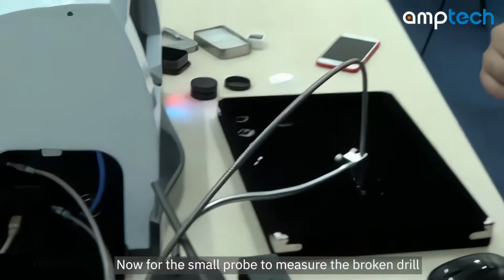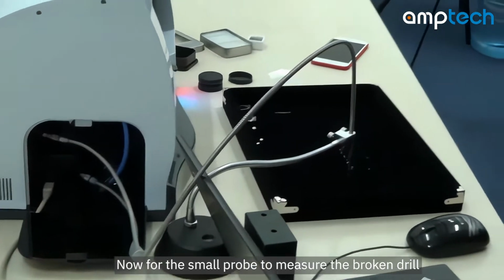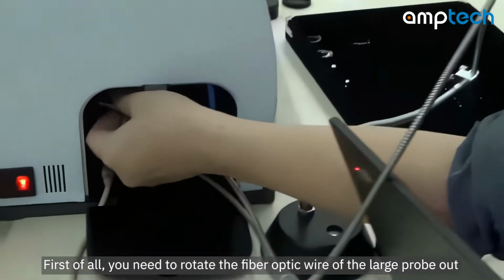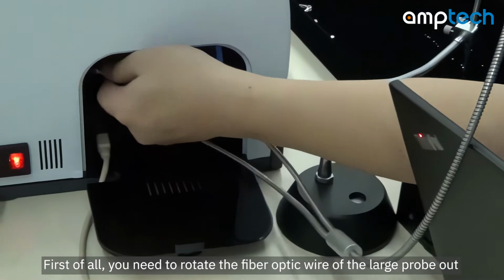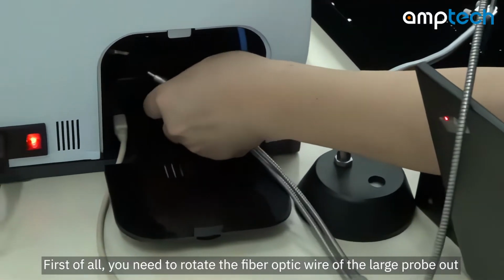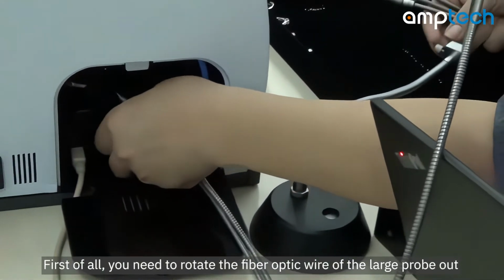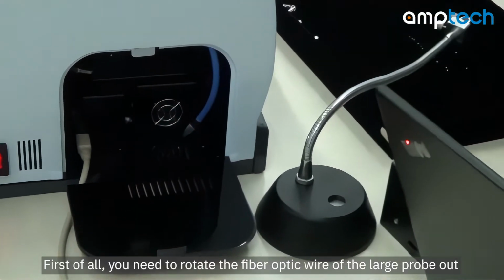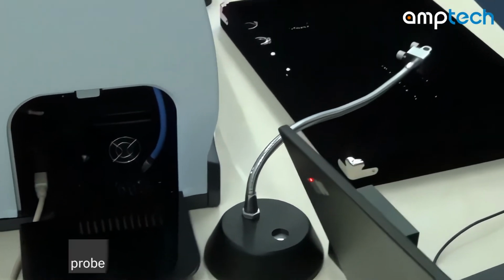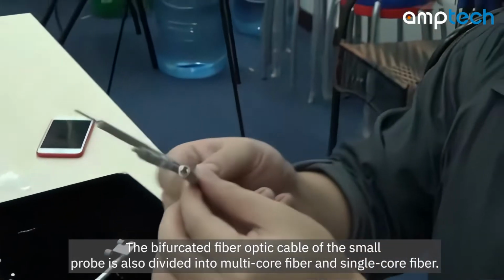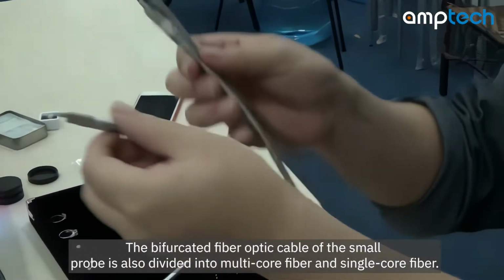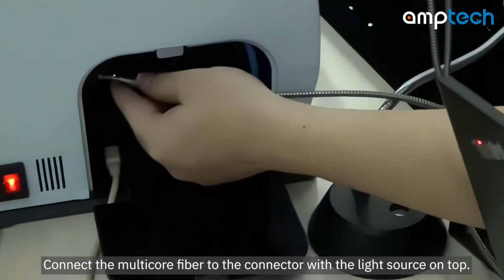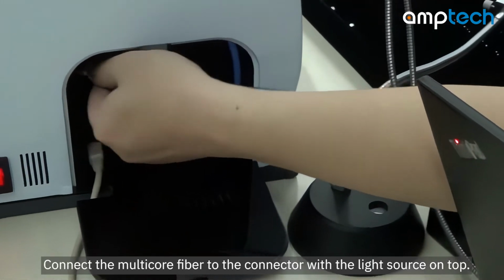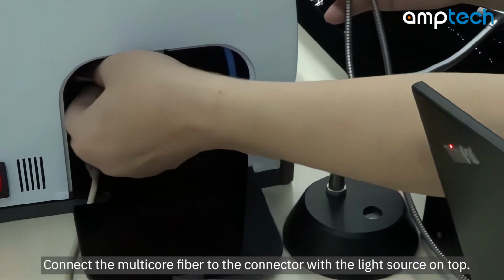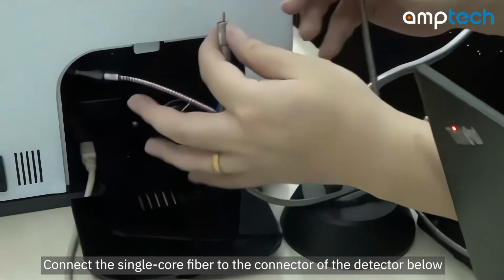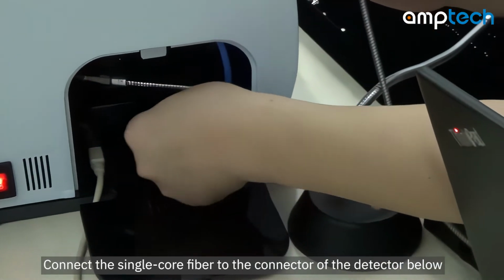Now for the small probe to measure the broken drill. First of all, you need to rotate the fiber optic wire of the large probe out. The bifurcated fiber optic cable of the small probe is also divided into multi-core fiber and single-core fiber. Connect the multi-core fiber to the connector with the light source on top. Connect the single-core fiber to the connector of the detector below.